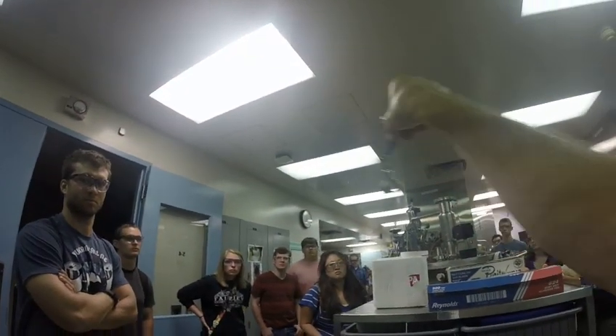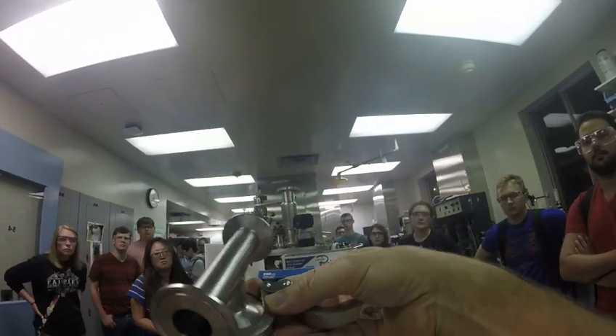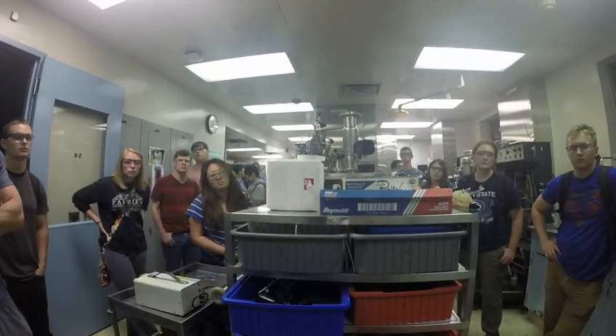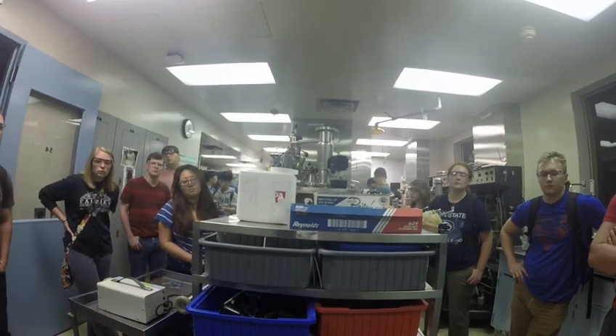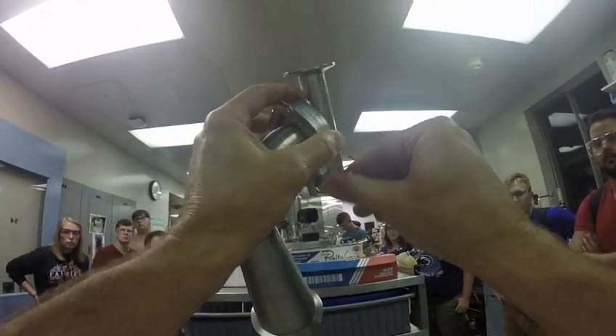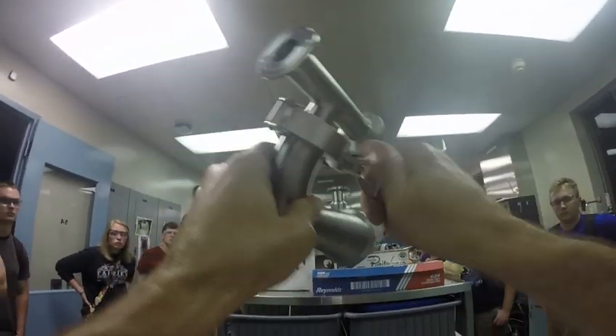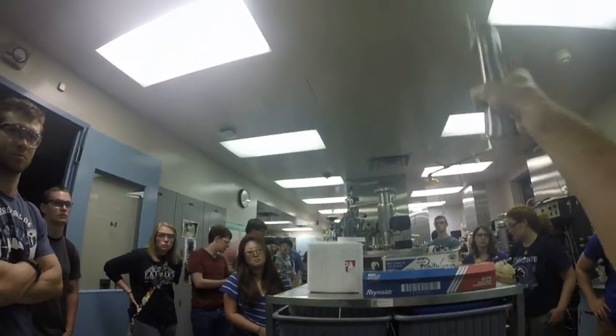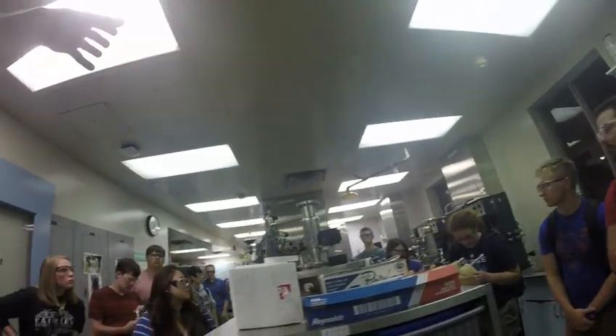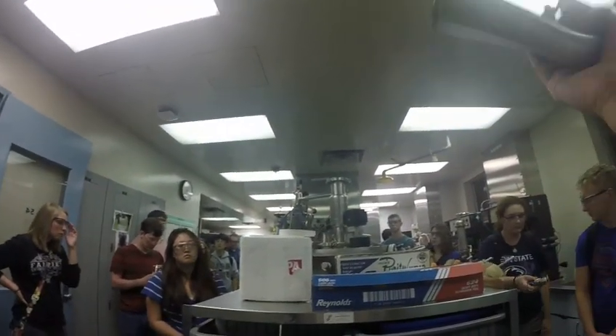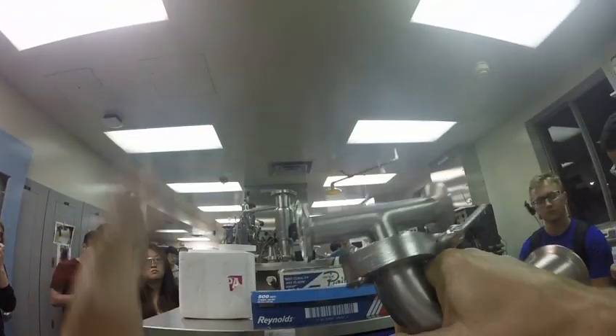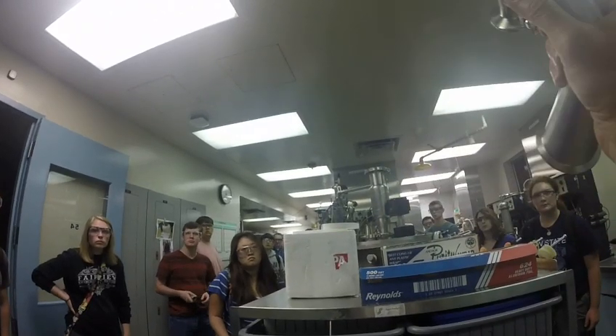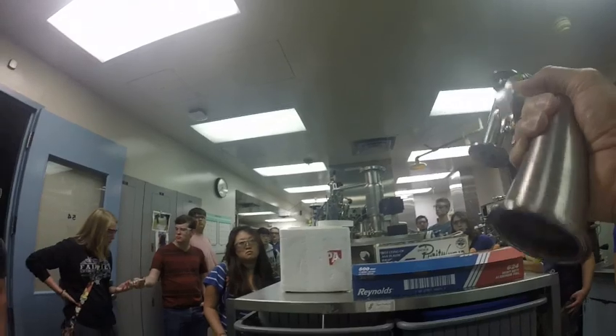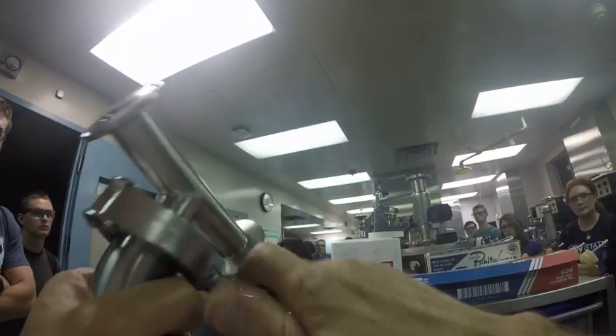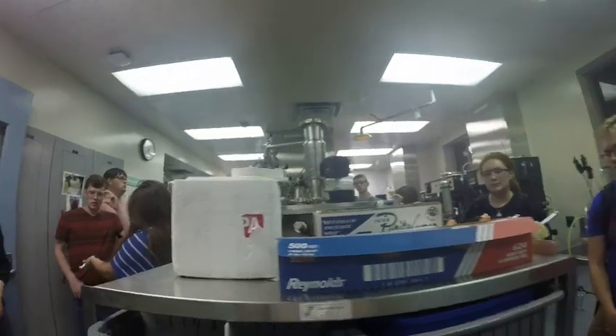There's a little bevel inside there that matches up with what's on the fitting. So when I pull this clamp over onto the unit, it gently pulls the pieces together, giving an aseptic seal. You'll notice that everything here, from the condensers to the probes, is put together with this type of fitting for two reasons: one, they can take a significant amount of pressure and won't give out, and two, they don't leak, because you can pull the clamp nice and uniformly snug onto the seal inside and assemble all your parts and pieces for that purpose.